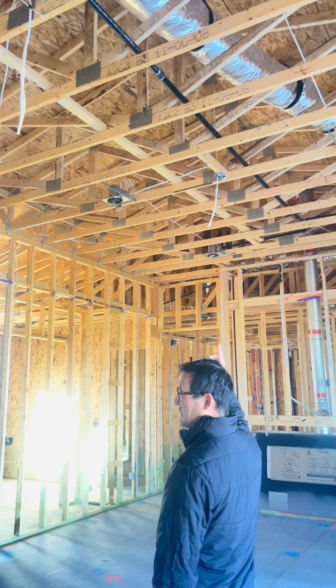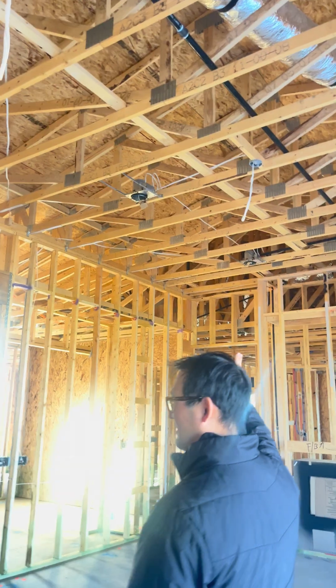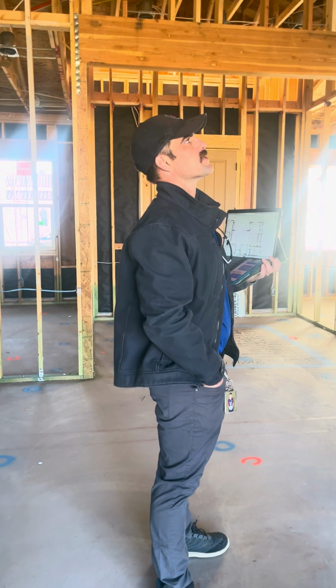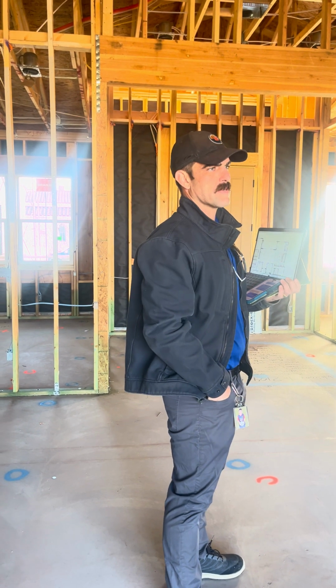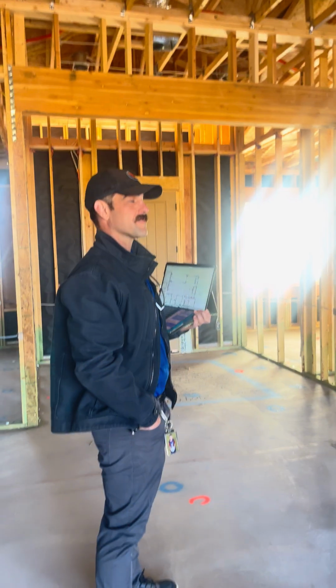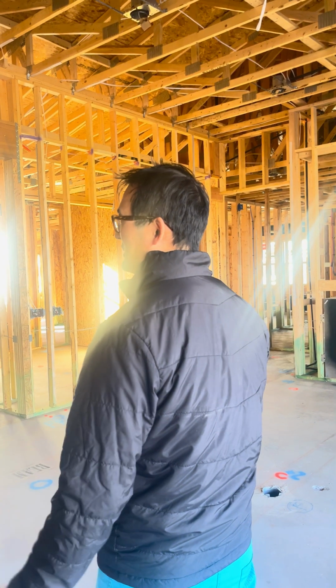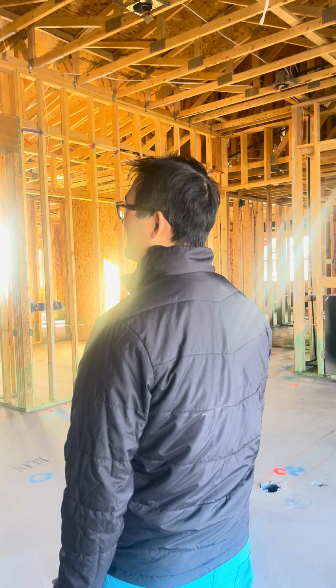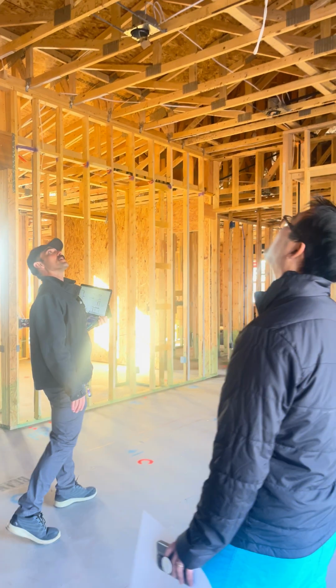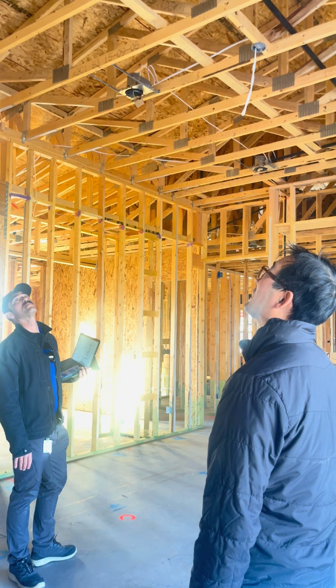Because these will probably be like bigger fans, is there a weight limit on them? Most fans are going to be well under 100 pounds. The ceiling fan boots that we use can accommodate a 100-pound fixture. I mean, technically it's 75 pounds, but we don't have problems with larger ones. In fact, most ceiling fans are going to be under 75, like a 55, 60 inch fan. Oh, you're talking about blade length. Yeah, you should be able to accommodate easily a 60, 72-inch fan. Quite a bit.